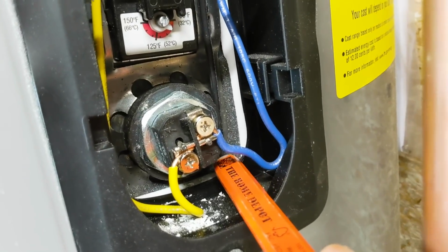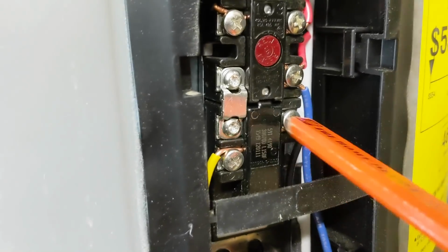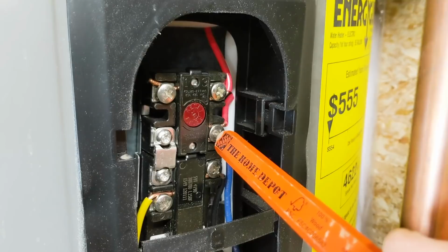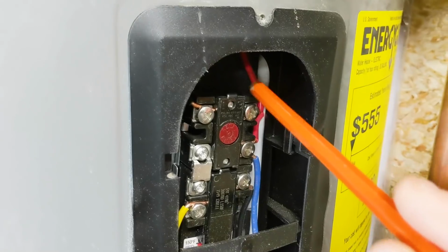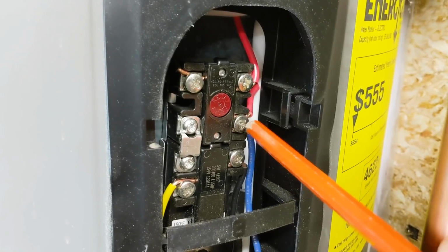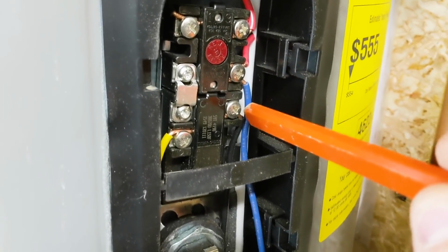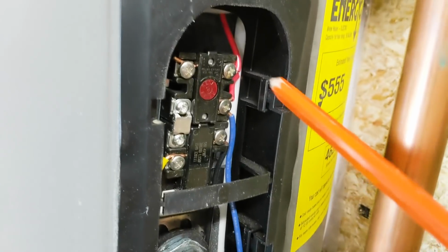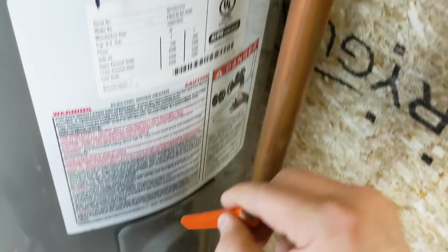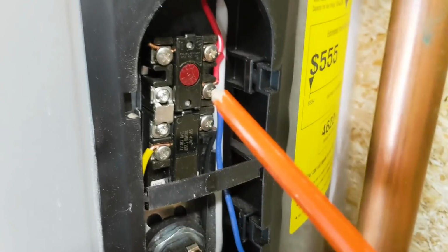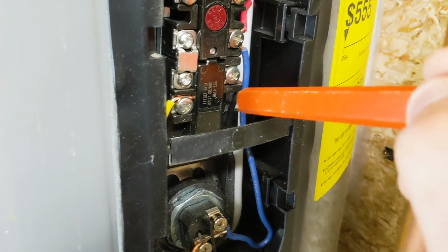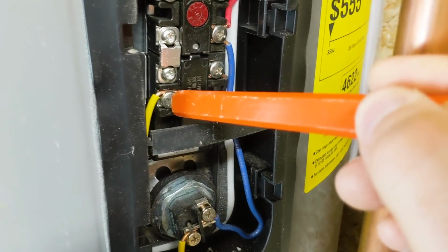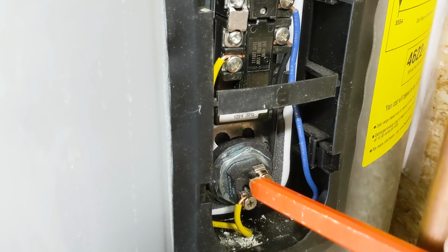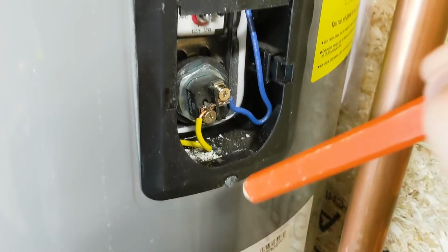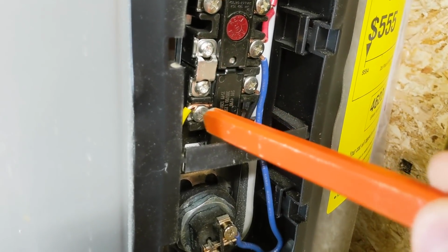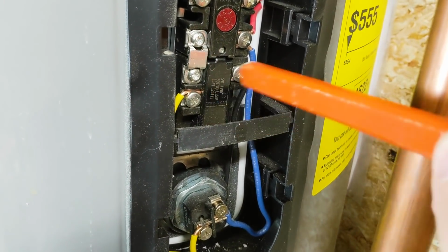Right back there is a black wire, and that black wire is coming off this screw. But we also have a red wire right here, also coming off this leg. So when the power comes in here, this side is always going to have that. So we have a red wire that travels down, and this blue wire which goes to this thermostat. So those ones are always connected, and it goes down here. What is switched though is this black wire right there, or this yellow wire. The yellow wire goes to the top heating element. The black wire goes down to the lower heating element. These are the screws that are being switched. Either this one is on or this one is on, and it's jumping between them.